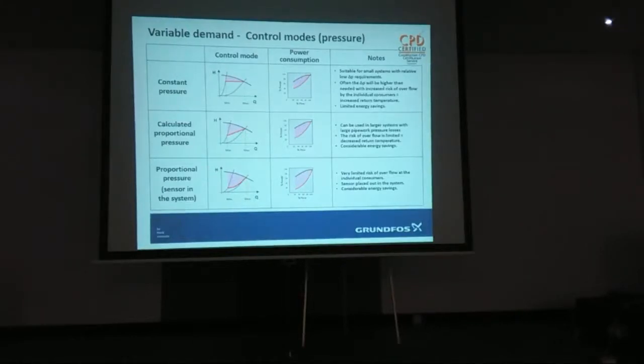And if you've got certain pressure snubbing devices, they'll take out any increase in pressure so you don't get any more water down the line, so you don't get any imbalance. But that is probably by far the best and most economical method, running on a differential pressure. It has to be differential pressure, it can't be single point pressure.